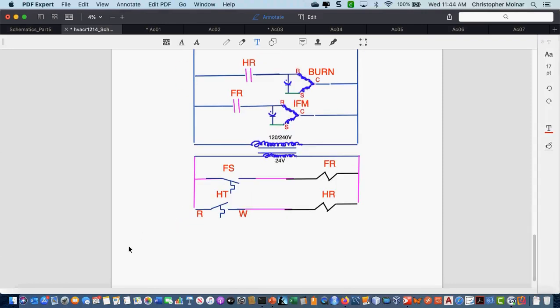That fan switch is part of a device that's called a combo fan limit switch. The combo fan limit has two temperature sensing devices in it. It has our fan switch to turn the fan on. It also has a limit switch, so we'll just say limit, and that prevents the furnace from overheating.